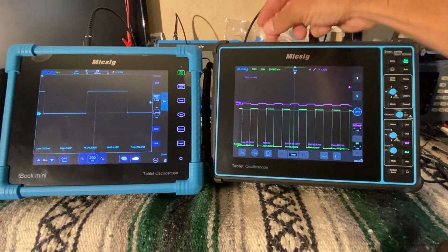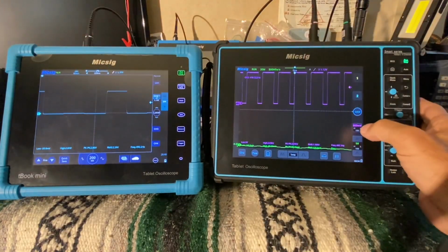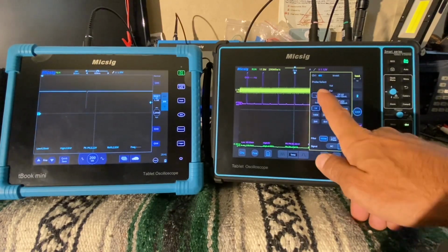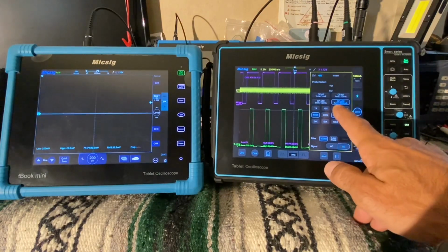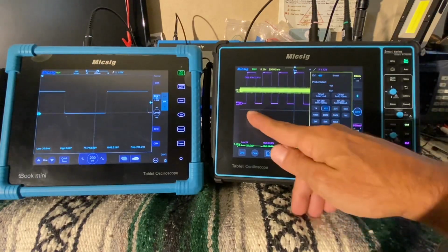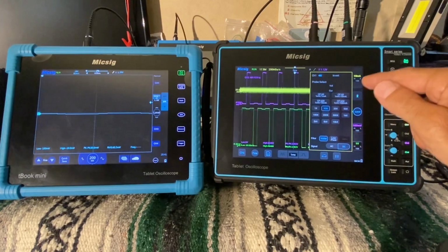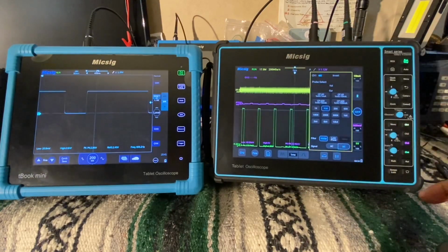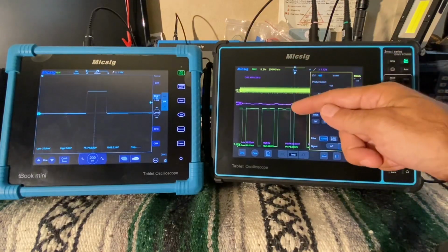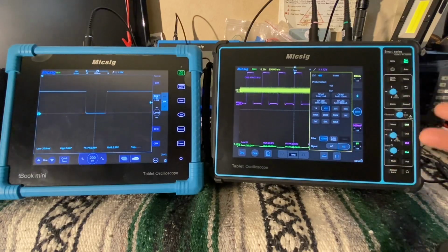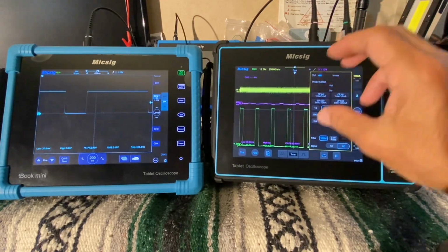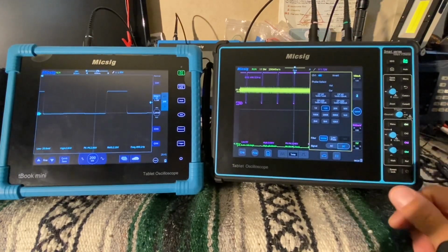So if you've been having problems, say we open channel 1 and we were going to set up current, if you're not positive how to set your attenuation for your current probe, because if you don't set it correctly, all your numbers are going to be off. You're going to get the same waveform. It may show 2 volts for your max, but since your settings are off, it could really be 4 or 6 or 8 or whatever. So with the new probes, it's going to set your attenuation automatically. I think that's really neat.